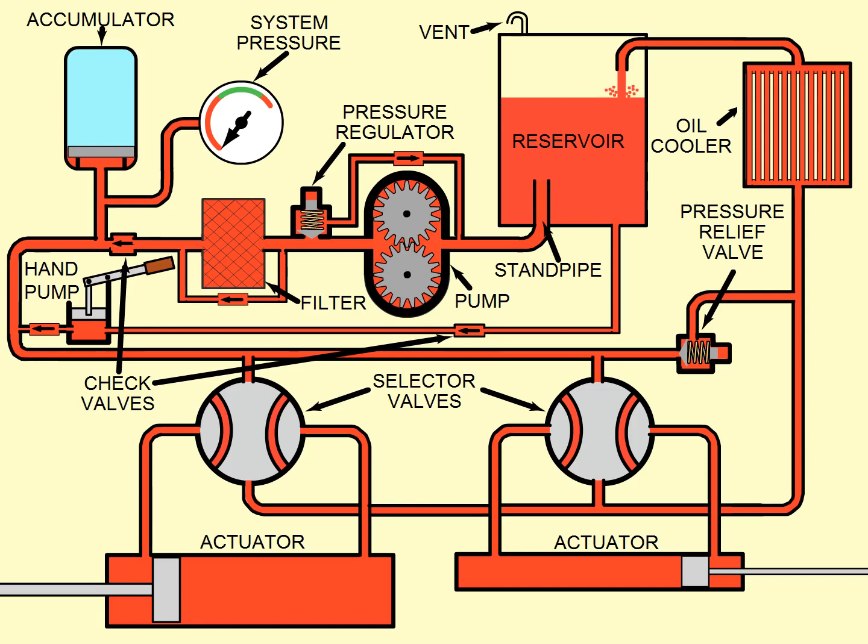At the moment, the pump is not running, so both the pressure regulator valve and the pressure relief valve are fully closed, and the accumulator piston is pushed fully down by the pressurized nitrogen above it, generally referred to as the gas pressure. The pump now starts turning, and as it does, it tries to push fluid into a closed system that is already full.